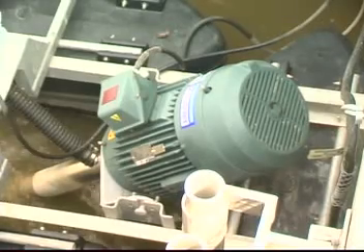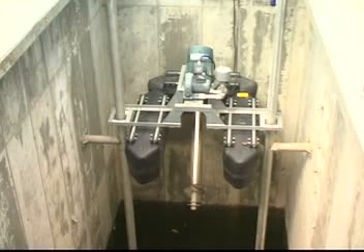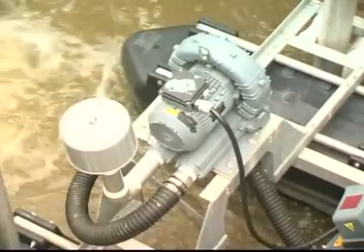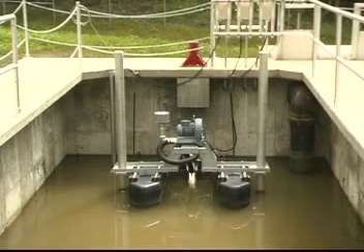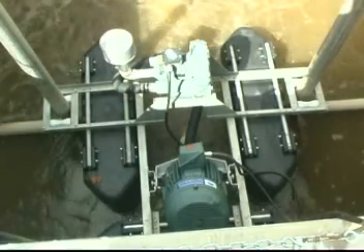The Triton consists of a 900 RPM electric motor coupled to a dynamically balanced hollow shaft and a unique two-propeller arrangement to optimize mixing and fine bubble formation. There is also a sealed regenerative blower on the system. The unit floats on pontoons and a slide rail system which accommodate the SBR's varying water levels and allow equipment inspection and maintenance to be done from the surface.